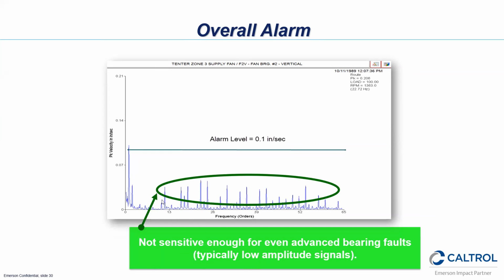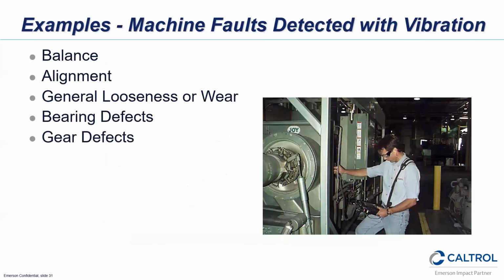As I was explaining, these are so low, they have value to us as we're looking at bearing fault frequencies, but they're not affecting the overall number because the amplitude's not high enough. Now they will, when they get to the point of failure, create enough amplitude that they'll trigger this alarm. Again, here are some more machine defects that are detected with vibration.